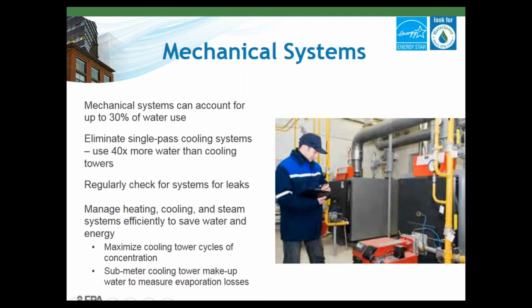With cooling towers, you lose water through evaporation. This is the primary function of the equipment, and it's not the focus of our water efficiency efforts. This is what they use to actually cool the water. The goal for cooling towers is more to, as I said, maximize the cycles of concentration, an indicator of the number of times the water has been recirculated before it's discharged to the sewer. One good thing is we have facility managers who are submetering makeup and blowdown water and detecting leaks to measure the evaporation losses, so they can actually understand and optimize their water use in cooling towers and boilers.